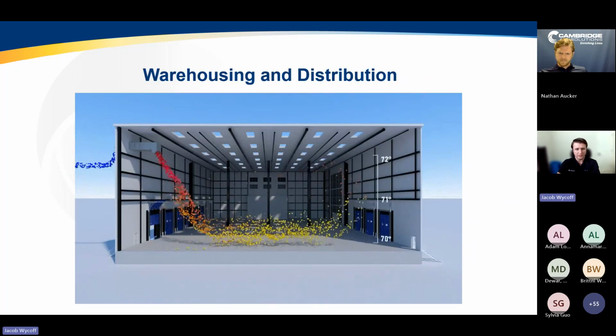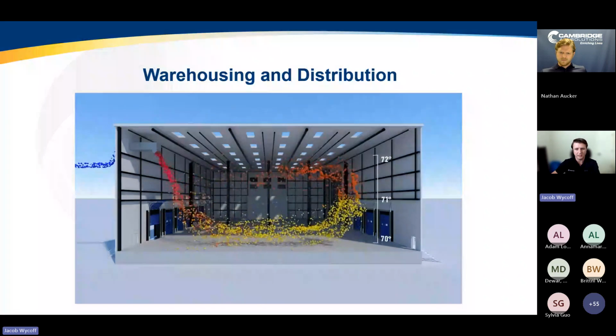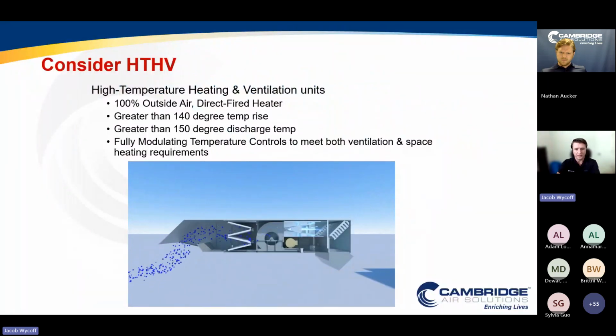Now, what about warehousing and distribution? As I mentioned, it's much easier to give specific guidance in these warehousing and distribution applications. We consider HTHV to be the best way to heat and ventilate these warehousing and distribution type spaces. So what is HTHV? HTHV is actually a definition created by the Department of Energy with specific performance requirements. That definition is: high temperature heating and ventilation units must be a 100% outside air direct fired heater with greater than 140 degree temperature rise, greater than 150 degree discharge temperature, and it must have fully modulating temperature controls to be able to meet both ventilation and space heating requirements.